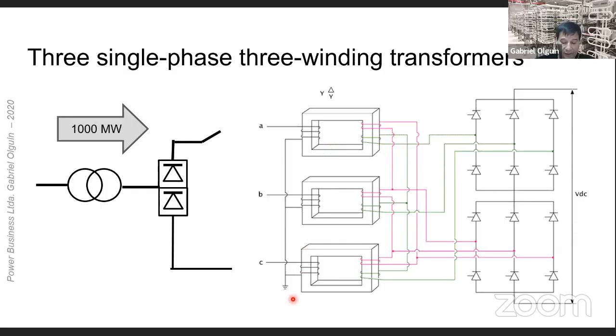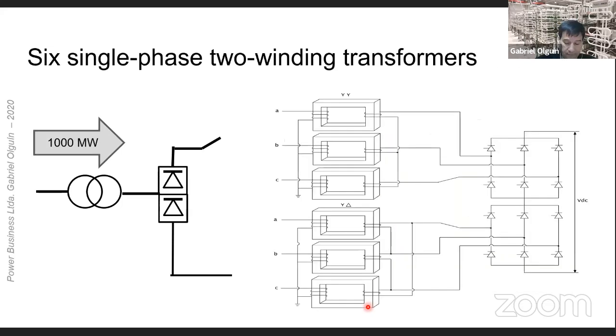Yes, right, grounded, while one of the 6-pulse groups is fed in delta and the other in Y ungrounded. If single-phase three-winding transformers are still too heavy or too large for transportation, then the only option is to use 6 single-phase two-winding transformers.